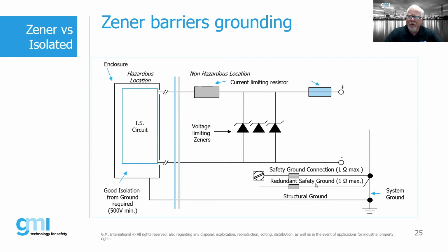The reason why you might use two, it's not a requirement, but it's good engineering practice, is that when you have to periodically test to see whether or not you still have 1 ohm resistance or less on your cables, you don't want to do that testing while it's connected to your Zener barrier. You want to disconnect it at that point and then make your connections and do your testing. If you disconnect that safety ground during a normal process, then obviously you've defeated the whole need for the use of an IS barrier, you've basically just defeated it right at that point.